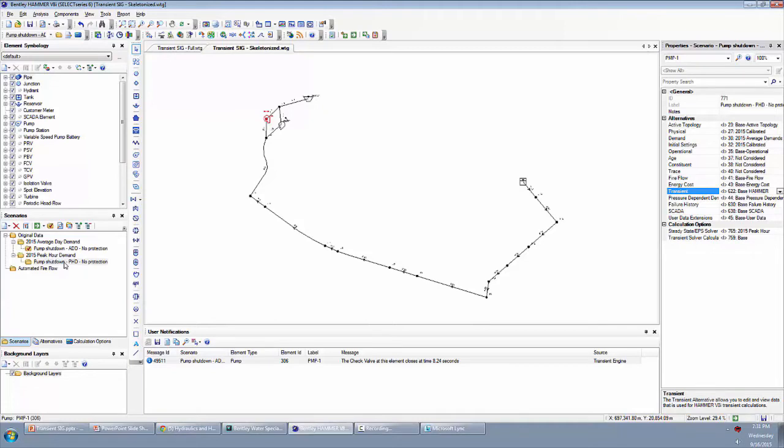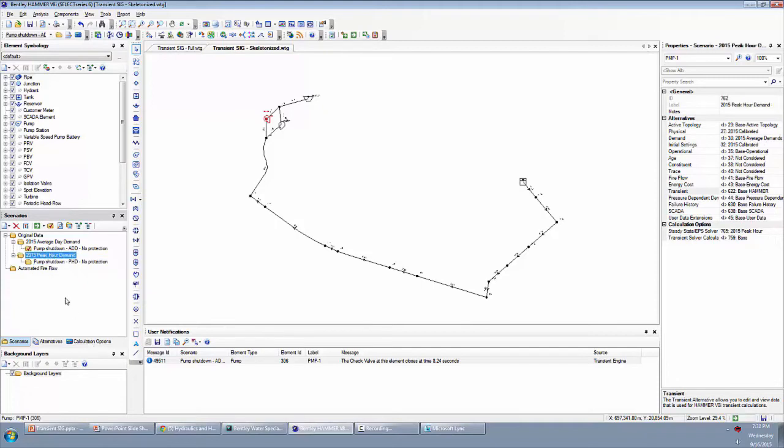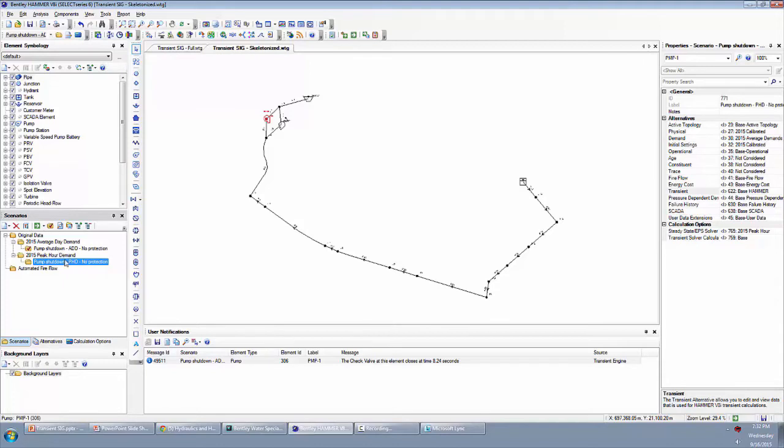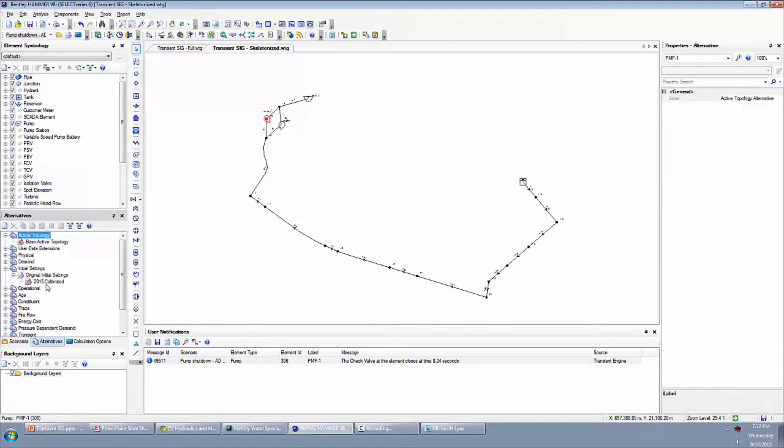The thing that we want to change in the peak hour demand scenario is actually the initial conditions because peak hour demand is actually a steady state simulation. So we want to make sure that we are starting the simulation at equivalent tank elevation that we tried in the other one. Remember when I graphed the tank and the pump, the tank was up near the top, it was actually at an elevation of 177.9. So what we want to do is make sure that this new scenario is using the same tank elevation to compare apples to apples. That's stored in the initial settings alternative.